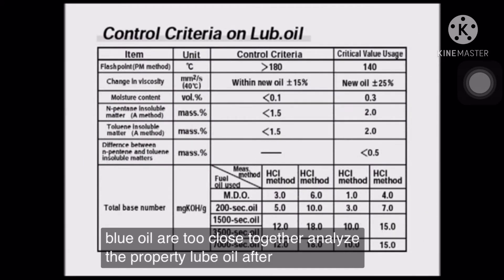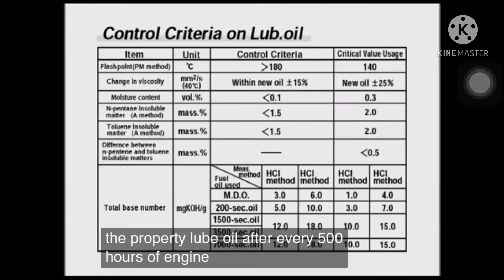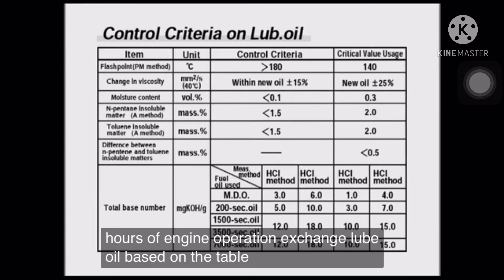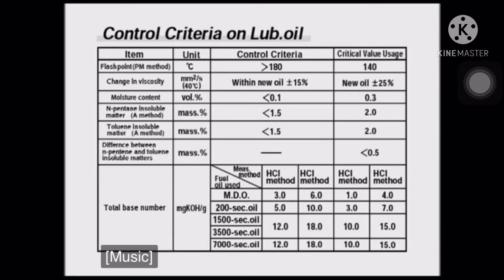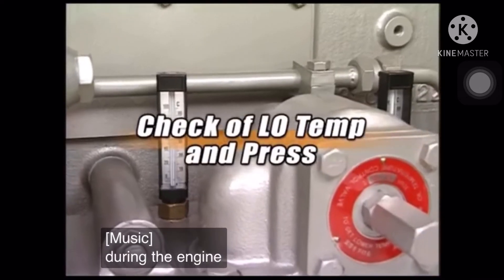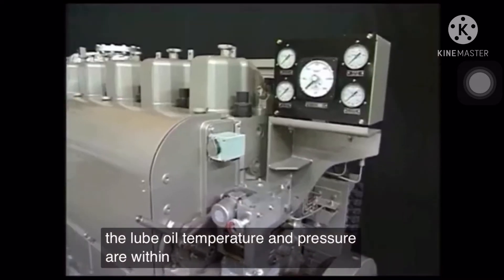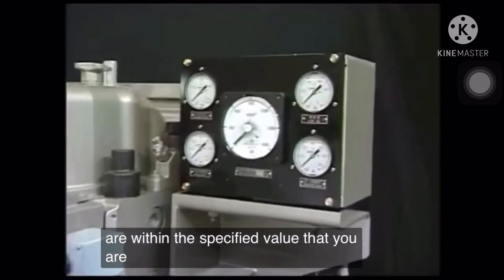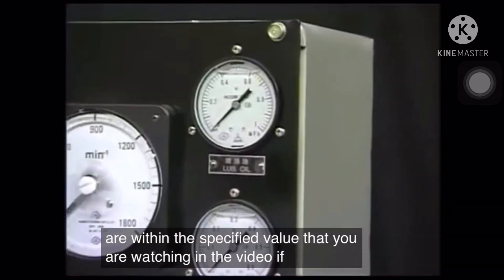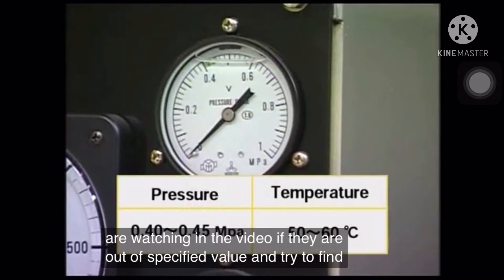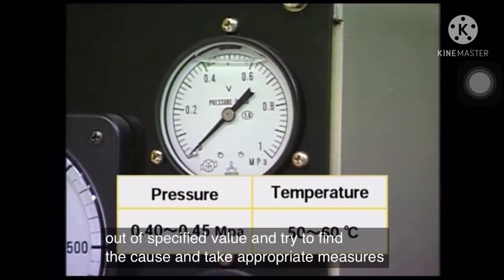Analyze the properties of lube oil after every 500 hours of engine operation. Exchange lube oil based on the table. During engine operation, check that the lube oil temperature and pressure are within the specified values that you are watching in the video. If they are out of the specified value, try to find the cause and take appropriate measures.